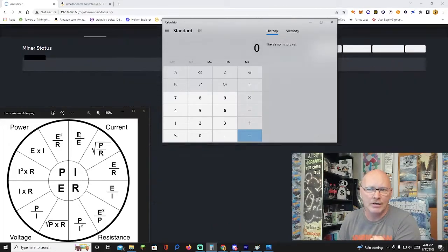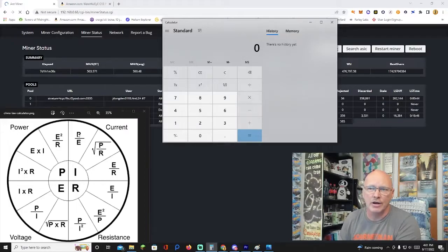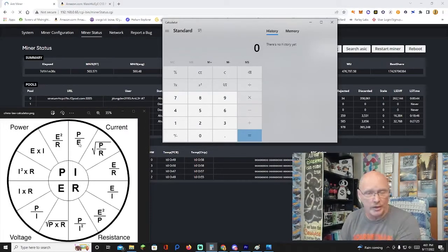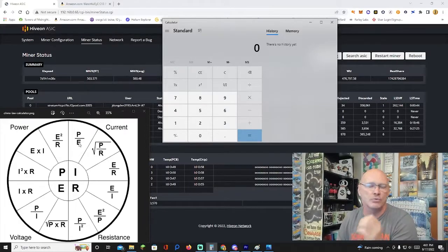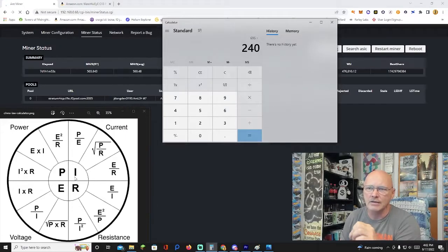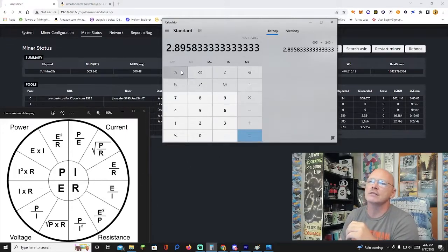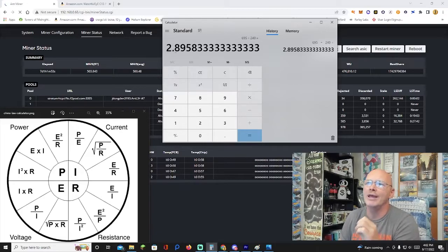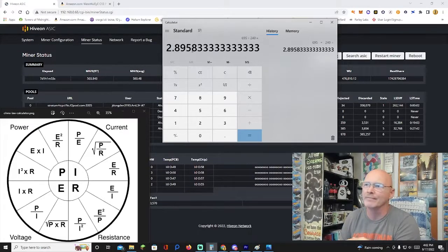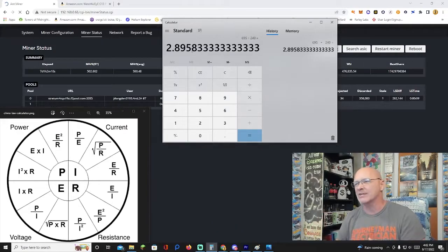So the power is our wattage. Well, we know that. That's 695. And E is our voltage. Well, we know that because we're running on a 240 volt circuit is what we're going to wire this up as. So all we do is go 695 divided by 240, which is our P over E, is going to give us our amperage. So that tells us this machine is running at 2.895 amps currently. Now, when I'm doing this and I'm planning a circuit out, I always like to give myself an extra little leeway. So I'm going to say this is running at 3 amps. I'm going to round it up just to give myself that extra bit.